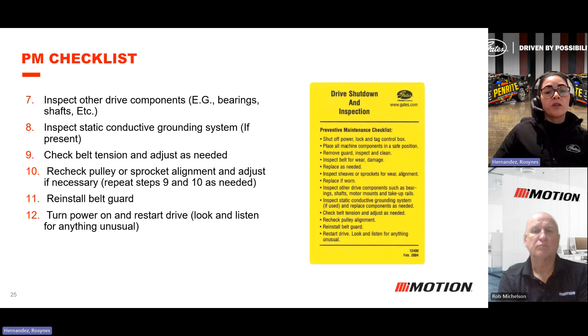Sometimes when you adjust the position of the motor, and then check the tension, you probably need to repeat this step a couple of times to get the proper tension, and also the alignment of the pulleys. Then after that, you reinstall the protection of the belt and turn it on. After you restart, you need to inspect and see if there is anything you can listen to or look at that is unusual. If something does not look right, or you hear a strange, unusual noise, just repeat your inspection again.